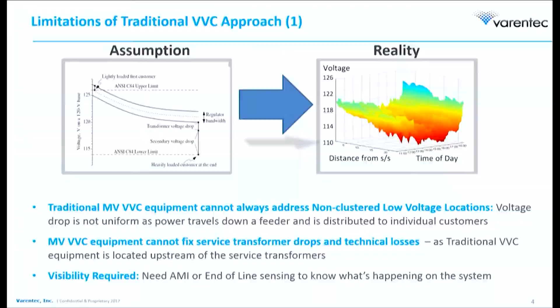So what's the limitation of that approach? If you look at the left-hand slide, the assumption behind CVR programs has been that voltage is reduced as you go down the feeder, and most low voltage customers are towards the end of the feeder. What we've seen, from data we collected on the right-hand side, is that this isn't entirely true. You could have low voltage pockets of customers anywhere in the feeder, the beginning, the middle, or the end. That type of condition, the MV equipment can't fully resolve. So you end up with these clusters of customers really limiting how far you can take the energy savings.